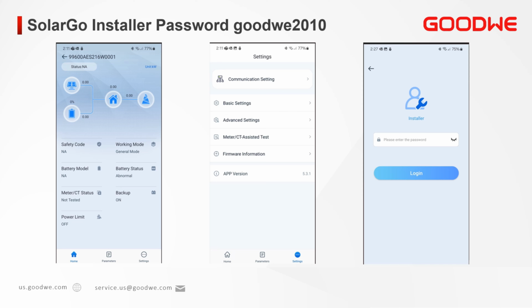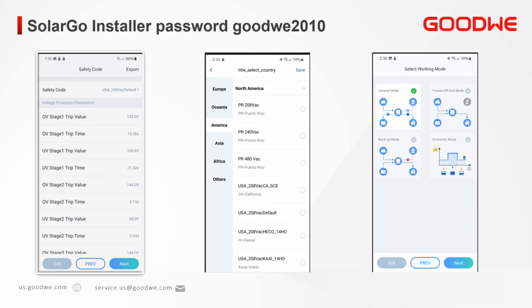For AES and ASB versions, the most common setting is the safety code. By default, it comes from the factory set to US 240 volts AC. If you need to change the grid code, then click on the USA 240 volts AC default and select. Once you've selected, click Save. Once you're back to the safety code, click Next. Now you are on the working modes. Select the working modes as applicable for this installation.